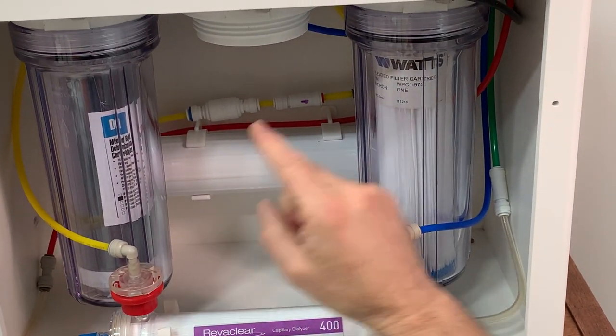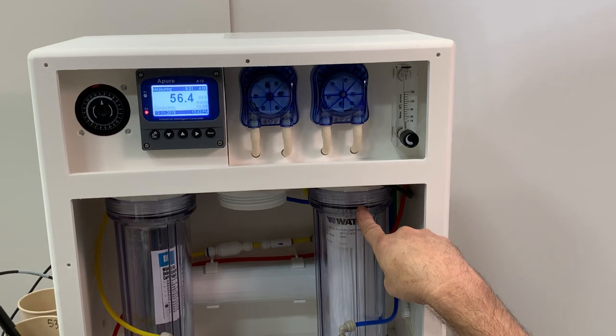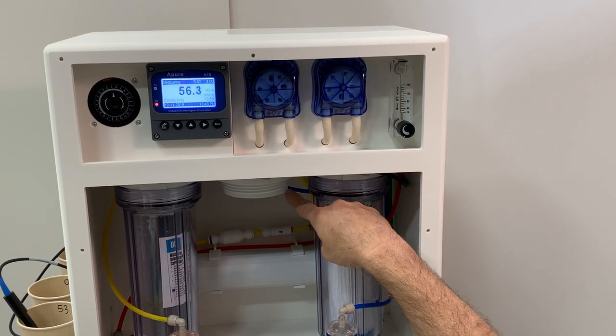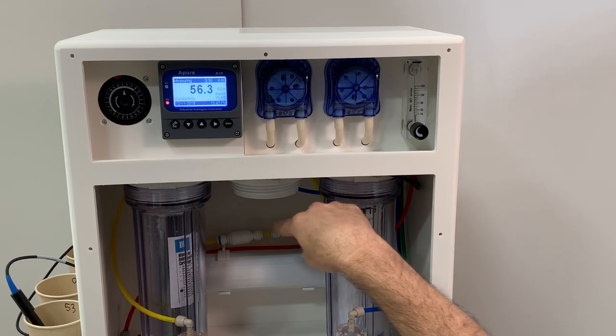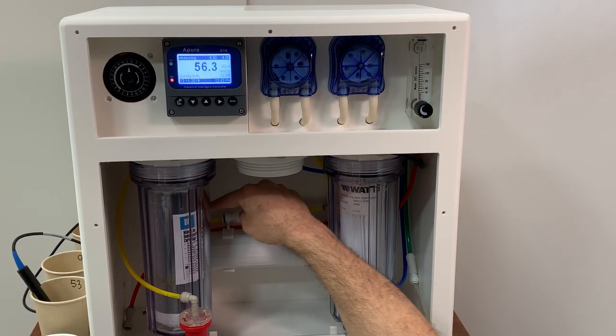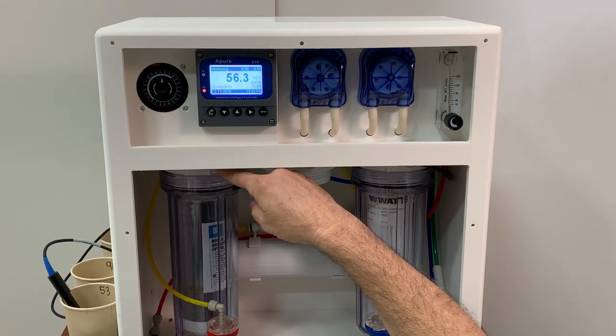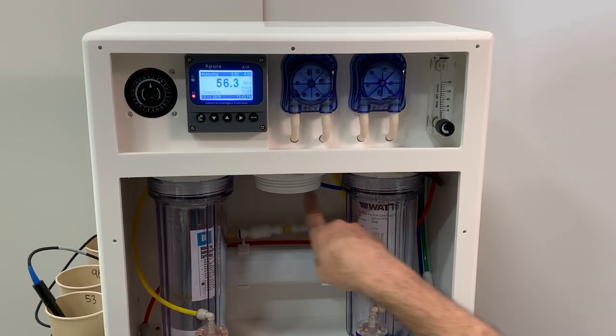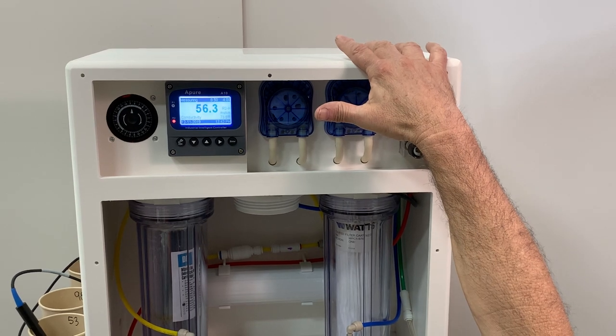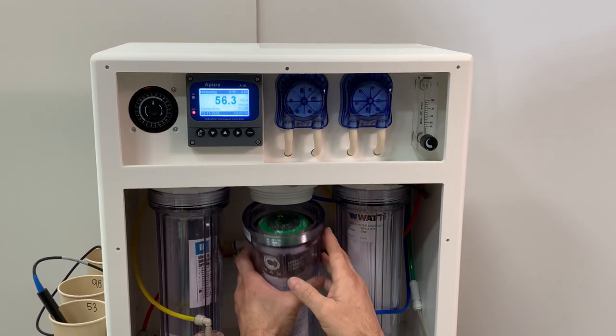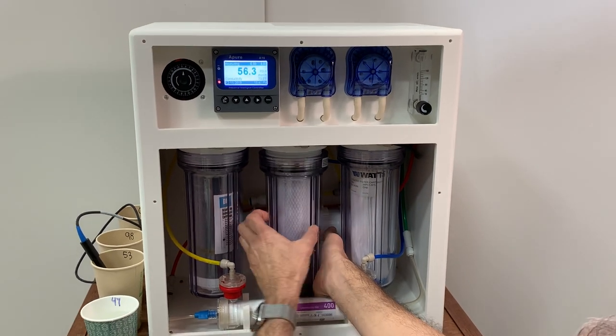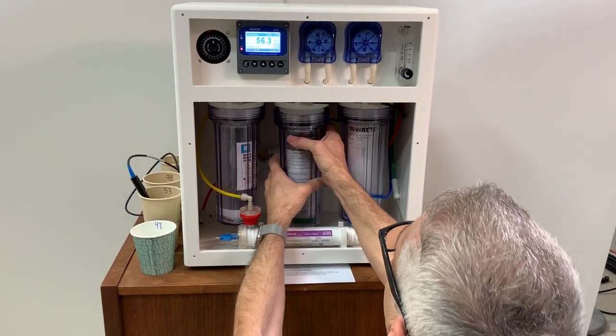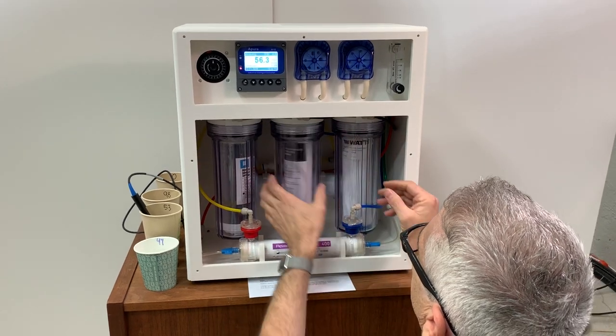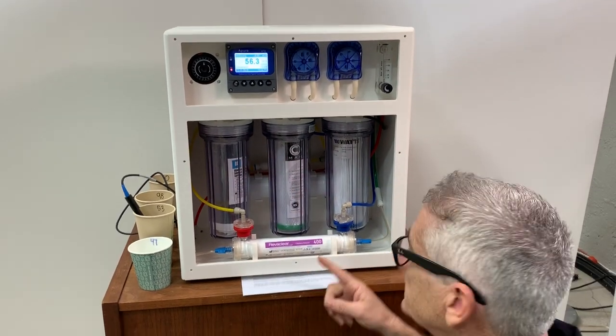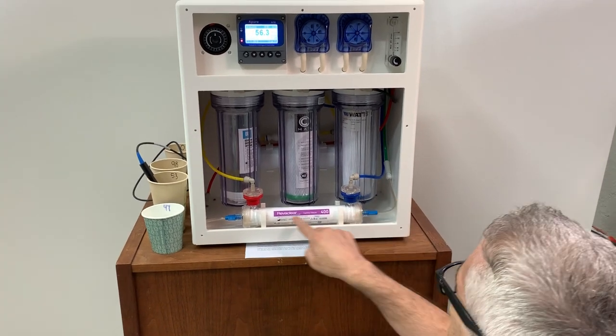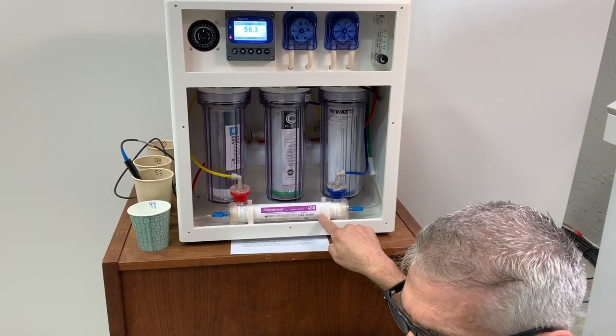So the sequence is the water will come in from the house water supply into your 1 micron filter, into your carbon block, from the carbon block to the reverse osmosis, out of the reverse osmosis, into the DI filter, out of the DI filter, up into the head unit, which I'll show you what happens there. So either we're going to be sending water to autofill, or we're going to be using that DI water to flush out the human artificial kidney.